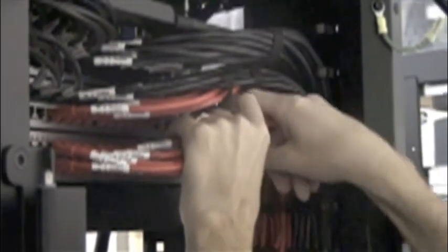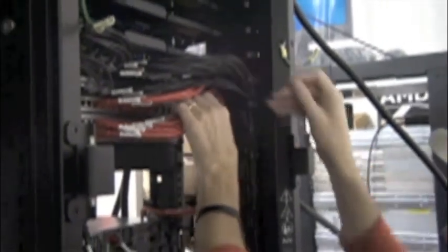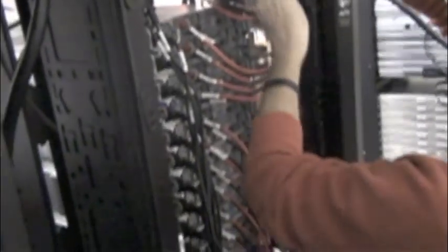The cables are laid out so that they do not obstruct airflow, because machines like this can generate a lot of heat. It's very important to get that heat away from the machine, so you want to have good clean airflow. Also, we lay the cables out so that these nodes can be removed and actually hot swapped. Each one of these chassis is 2U, and it has 4 nodes in each chassis, but if one of those needs maintenance, you can hot swap it out, and there's a very clear path for that. So it's that kind of thing that can really make a difference.